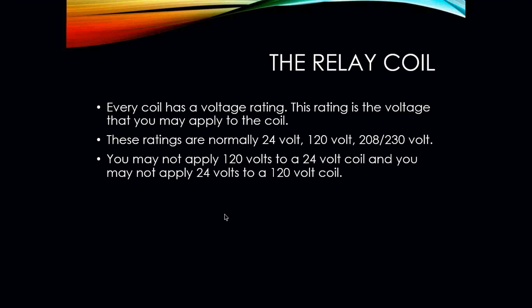If you were to apply 120 volts to a coil that was rated for 24 volts, you will melt the coil. You will probably set the coil on fire. You're going to damage the coil. You're going to damage the relay no matter what. If you were to apply 24 volts to a coil that was rated for 120 volts, you would not generate enough magnetic field to change the armature to open and close the contacts.